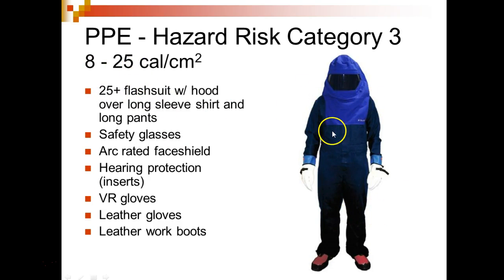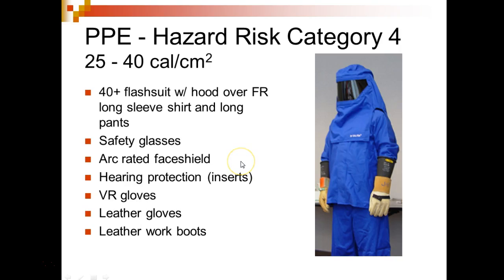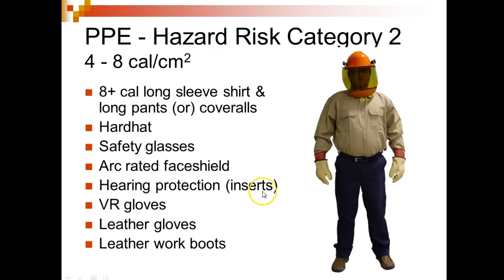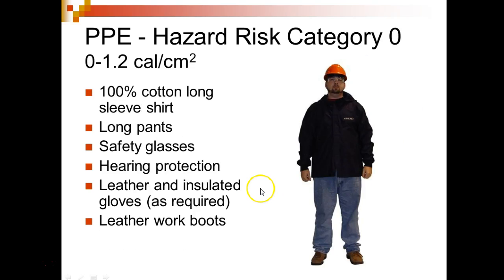This is when you start putting on your bunny suit, right? 25+ rated hoods over long sleeve shirts and long pants, safety glasses, hearing protection. Okay, then you get into this one right here. Then you've got a flash guard hood over fire resistant long sleeve shirts, long pants, safety glasses, hearing protection, voltage rated gloves, leather gloves. So you've got rubber gloves rated for the voltage, then leather gloves over that. So what PPE you get into depends on what calorie level you're in. So here we're below 50 volts. This actually comes into play over 50 volts. So we're requiring you to wear long pants and no open toe shoes.